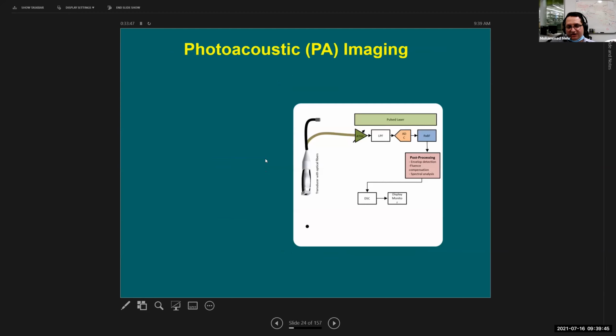All right, so another demonstration. This time I'm showing you why we call this ultrasound-based modality, because everything we do, all the signal acquisition of those photoacoustic generated waves, is done by a normal clinical ultrasound transducer. So I have my ultrasound transducer, similar to the handheld probes you see in clinic. And all I did is put a pulse laser next to it, and I deliver the light to the same imaging plane that my ultrasound probe sees. So if my ultrasound probe sees this plane, I try to illuminate or irradiate the same plane.